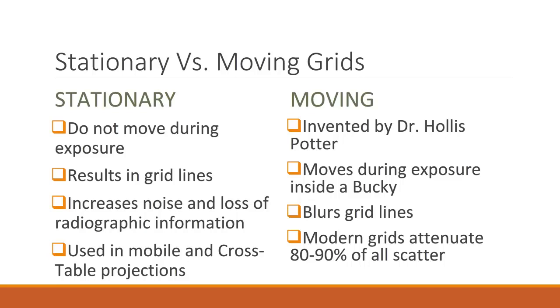Modern grids have come a long way and are capable of attenuating 80–90% of all scatter radiation. Other grid variations include how the lead strips are arranged. A parallel grid has strips that are vertical and parallel to one another, while a focused grid has the lead strips at a slight angle to better align to the divergence of the x-ray beam. This is called canting of the lead strips and is common in most modern-day grids.